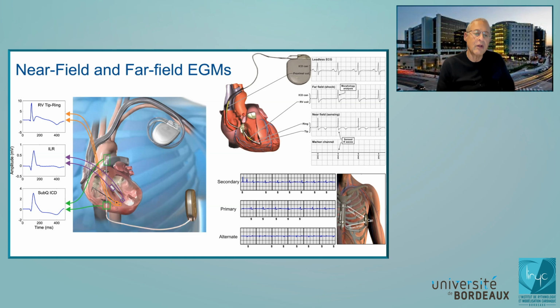And so when Medtronic shows you these signals and you see them going from 3 millivolts down to 1 millivolt, you should have in your head that the actual signal that is filtered, rectified, and analyzed and compared with a sensing threshold is considerably smaller than the one you're actually looking at. Pierre, I could spend an hour on this subject, but is that good enough for this part of the talk, and we could come back to more at the end?